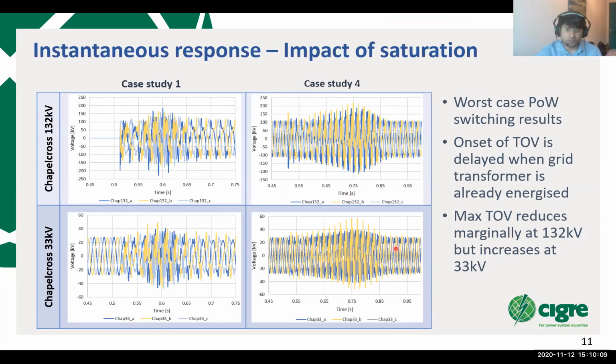So what this tells us is that we do not have a clear answer to whether energizing a transmission line with the grid transformer will always lead to a favorable result at all the bus bars. It can potentially help in case of overvoltage in some of the bus bars, but it might make it a bit worse in another part of the network.